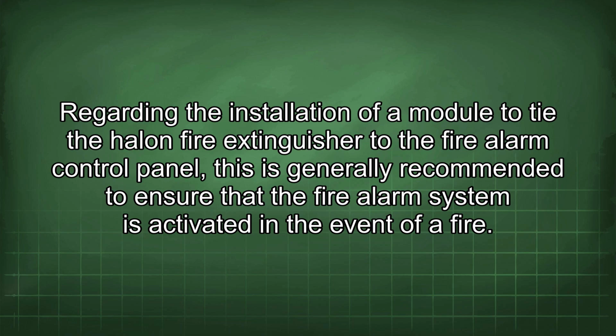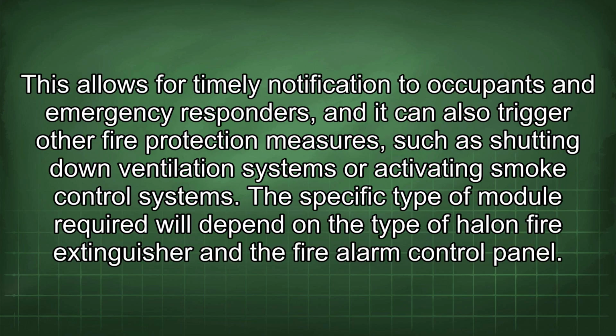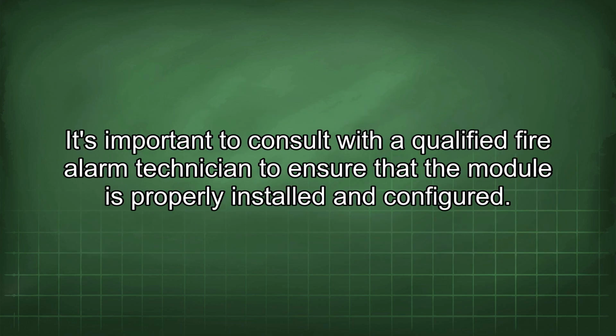Regarding the installation of a module to tie the Halon fire extinguisher to the fire alarm control panel, this is generally recommended to ensure that the fire alarm system is activated in the event of a fire. This allows for timely notification to occupants and emergency responders, and it can also trigger other fire protection measures, such as shutting down ventilation systems or activating smoke control systems. The specific type of module required will depend on the type of Halon fire extinguisher and the fire alarm control panel. It's important to consult with a qualified fire alarm technician to ensure that the module is properly installed and configured.